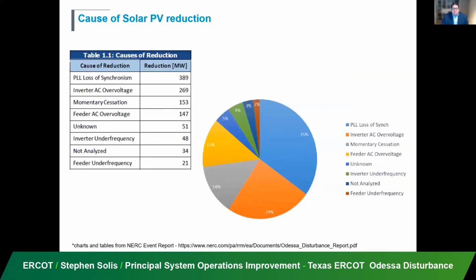When we look at the causes, and I want to pause here and take a little bit more time on this slide. The primary or leading cause that we saw as far as impact were really two things. One was PLL, loss of sync relays, or phase lock loop protection that really shouldn't have tripped off those units, but we did see that we had about 389 megawatts of lost generation due to that. And then when we look at overvoltage, both at the inverter and the feeder level, we saw units trip off due to overvoltage, their high voltage ride-through mode.